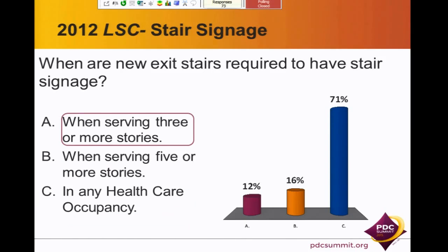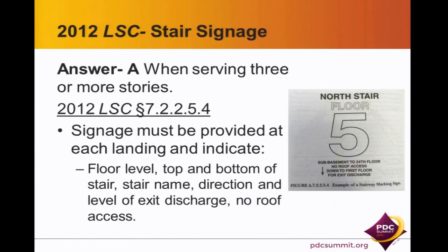The correct answer is A. When serving 3 or more stories. In an existing facility, it's 5 or more stories. So that's where that response to question B comes in. But if you have a healthcare occupancy that is only 1 story, you're not required to have that stair signage. And actually on the next slide, Bill, here's an example of the stair signage. This is provided. Is there a question?